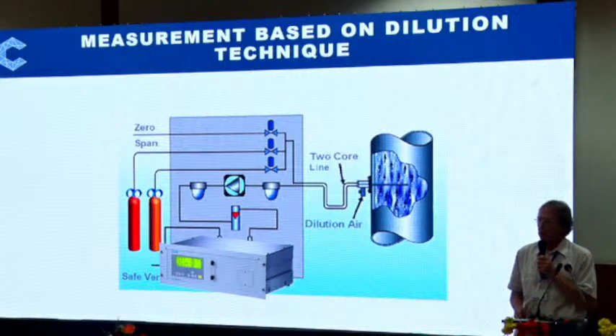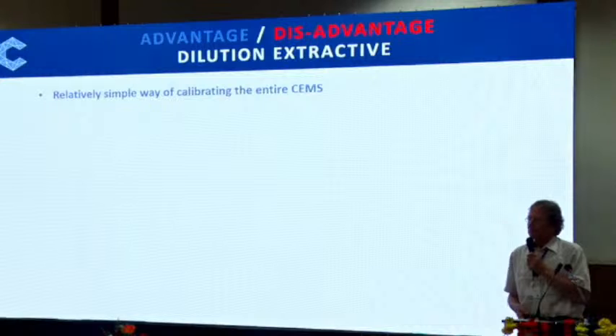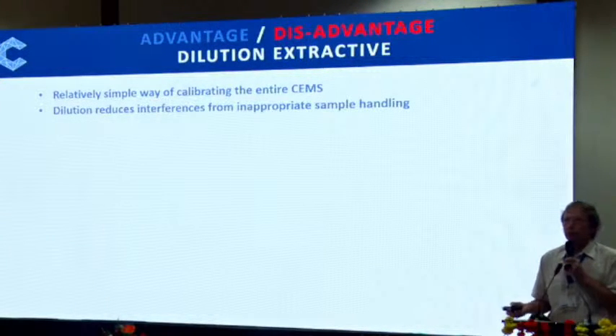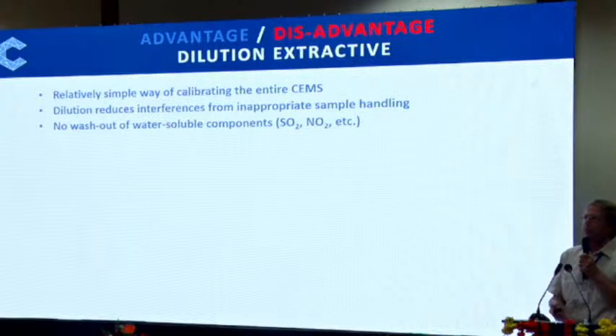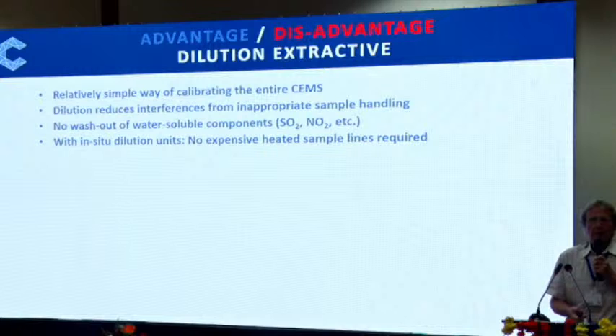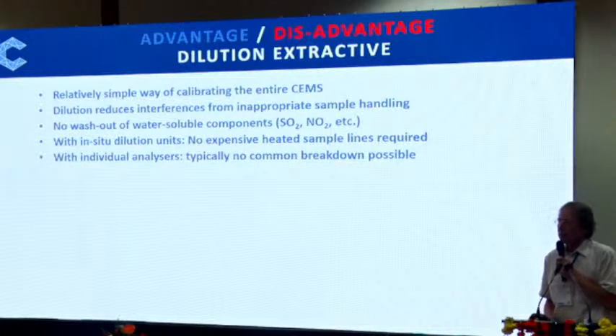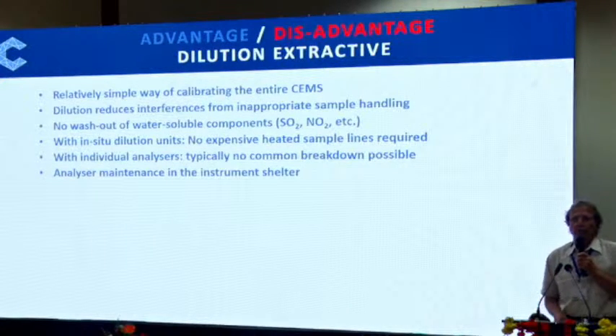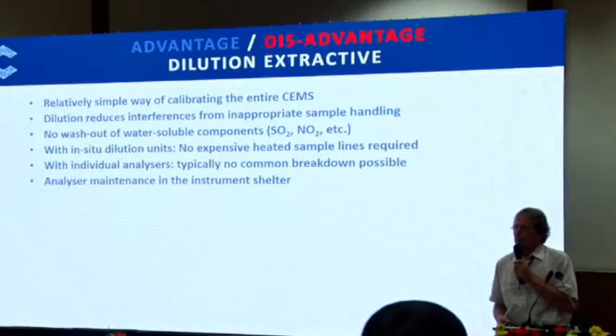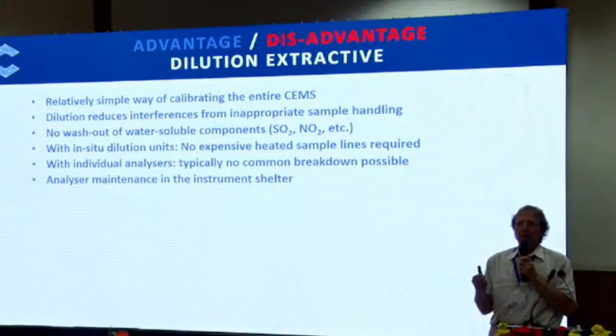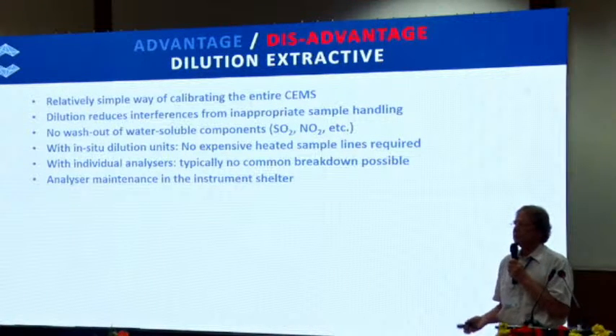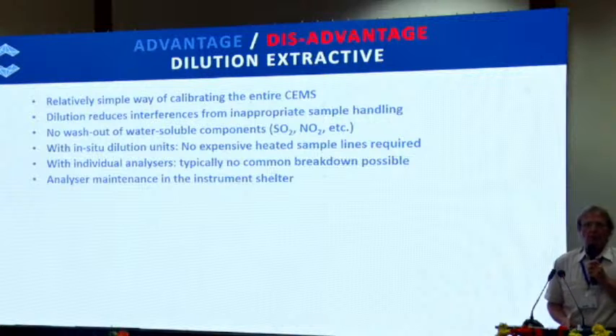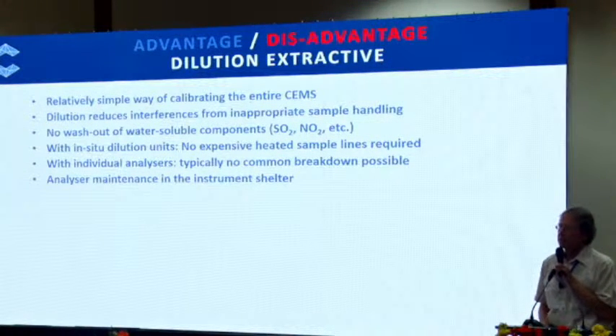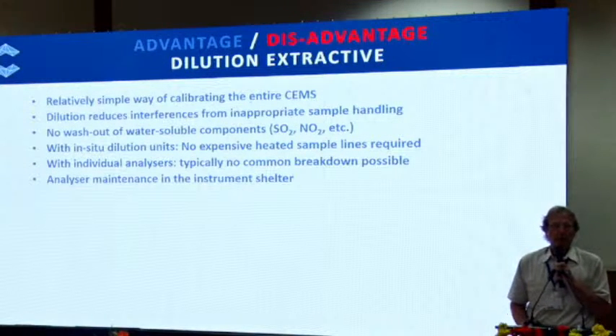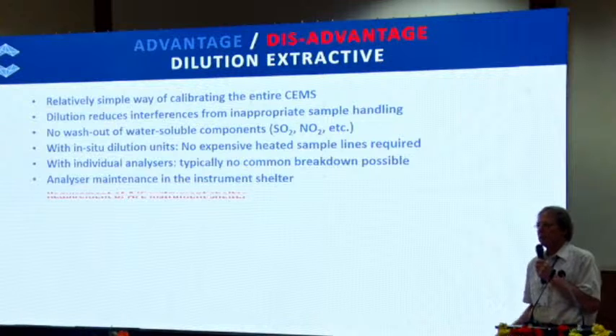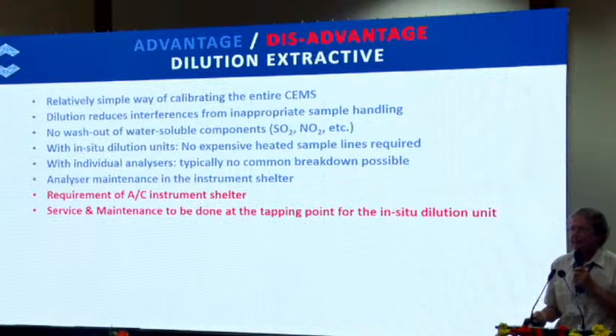Last, in situ dilution or ex situ dilution. Very simple to calibrate it, because I introduce a calibration gas at the dilution probe. I calibrate the analyzers, including the dilution factor, in one step. I have no loss of water-soluble compounds, no washouts. I do not need any heated umbilicals, so a very significantly lower cost factor, especially when we come to long heated sample lines or long distance. I have individual analyzers, and the service and maintenance for the analyzers is in the AC shelter. I again need an AC shelter.